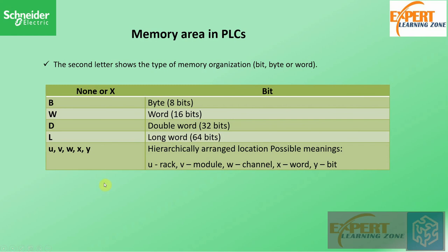There could also be a case where we are interested in accessing just a bit, in which case we use a hierarchical notation where variables are expressed as %U.V.W.X.Y — where U is the rack number, V the module, W the channel number, X the word, and Y the bit. We will see how this is implemented in software, and it may change slightly depending on the implementation or configuration.